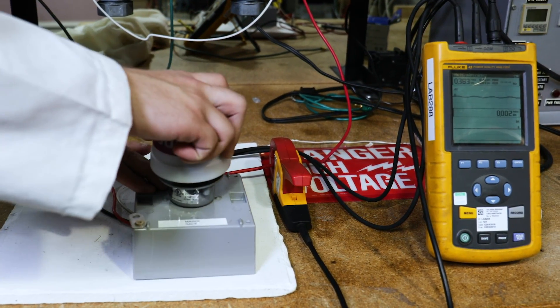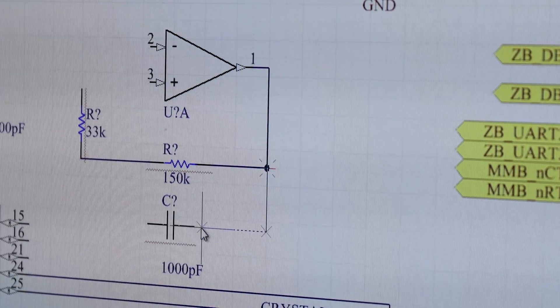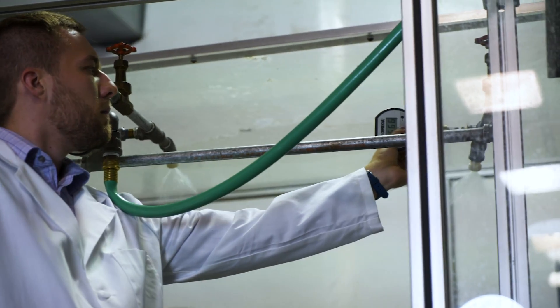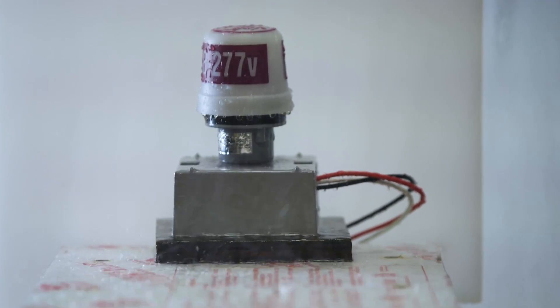We've tested beyond its ratings. We help engineers early in the design and throughout the entire design process, so we know it'll comply with our electronic ballast testing. They design in certain mechanical features knowing it has to comply with our rain test, and they check different light levels knowing it must comply with our ANSI C136.10 light level testing.